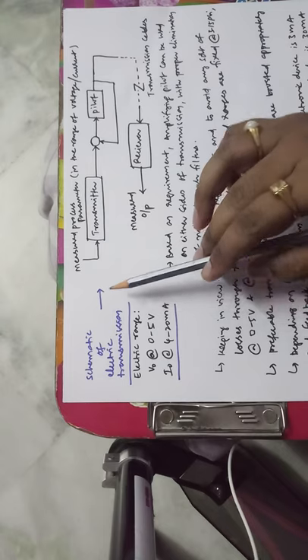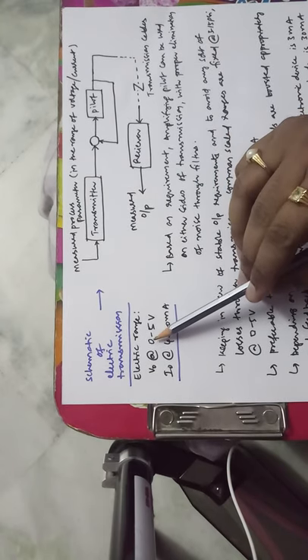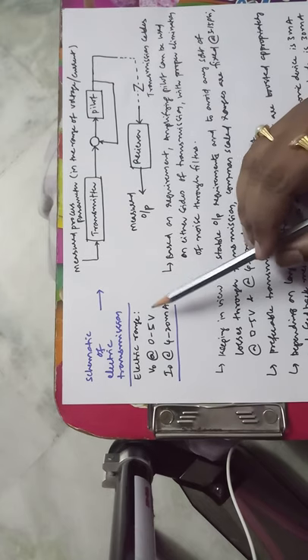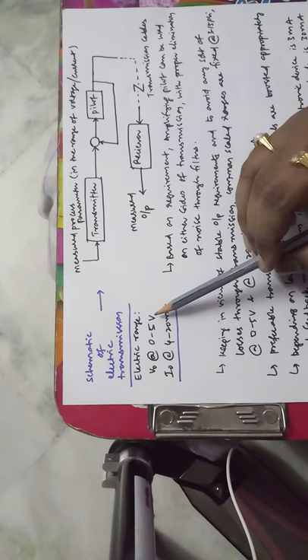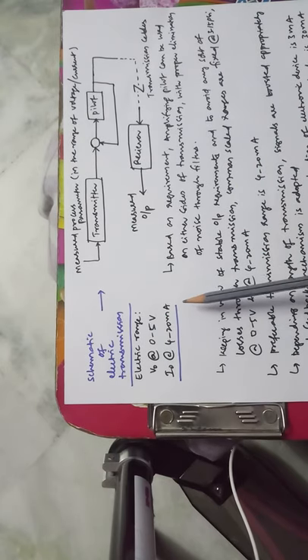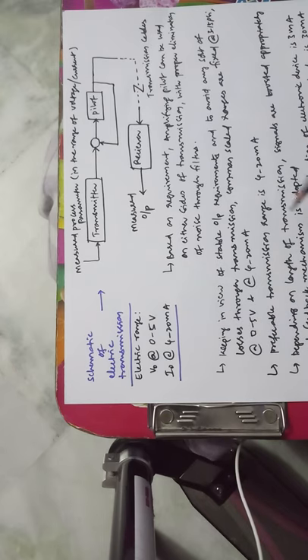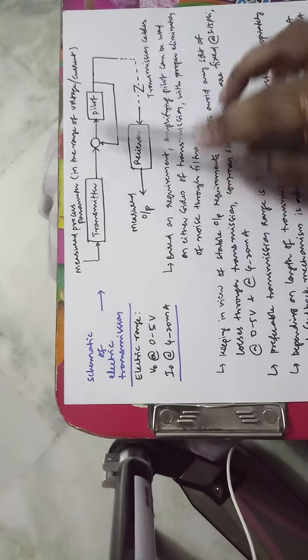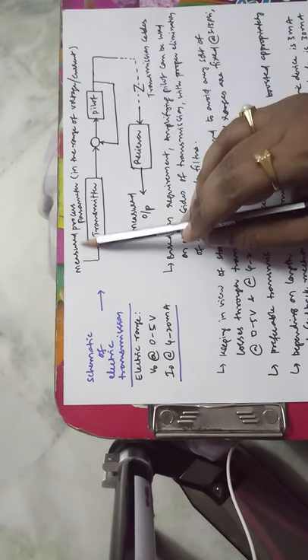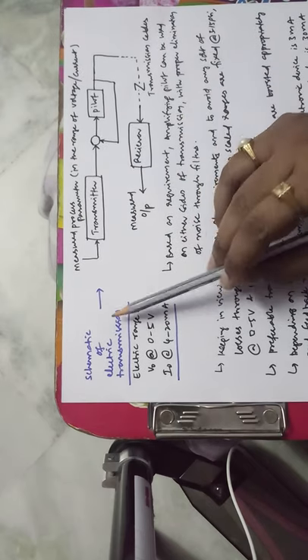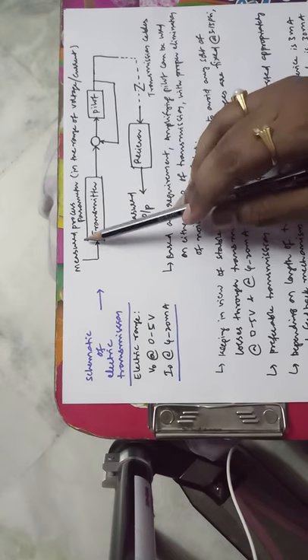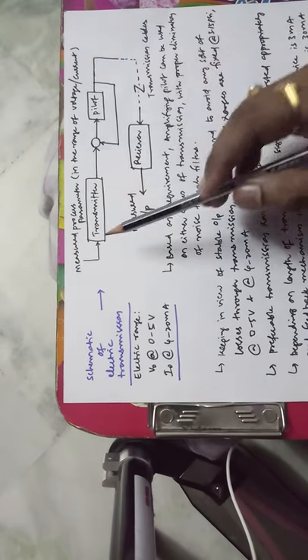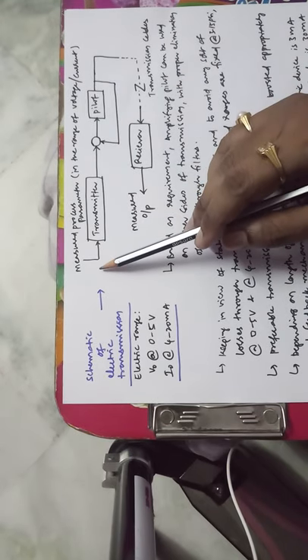Similarly, we can have an electrical transmission system where the electrical range will be 0 to 5 volts for voltage, or 4 to 20 milliamps for current. In pneumatic transmission, the measured process parameter is in the range of pressure. In case of electrical transmission, the measured process variable is converted into the range of voltage or current.